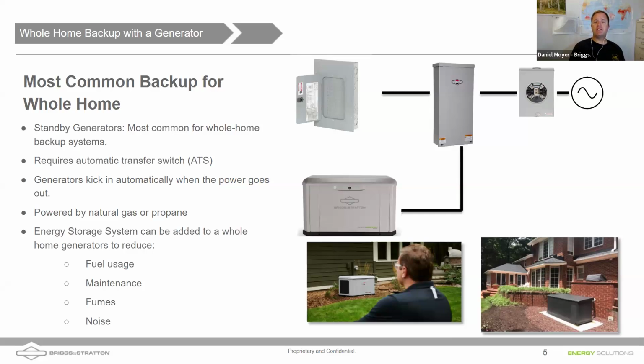There's a lot of advantages to using this historic way to do it. There's always a lot of power, and usually if you have natural gas or a 1,000-gallon propane tank, it's in a lot of ways unlimited fuel. That being said, there are options now with these much more high-powered inverters, such as the Sol-Ark 15K, where we can combine energy storage systems and generators together. You can reduce fuel usage, reduce some of the noise and fumes associated with generators, and also the maintenance associated with long run hours on these generators.